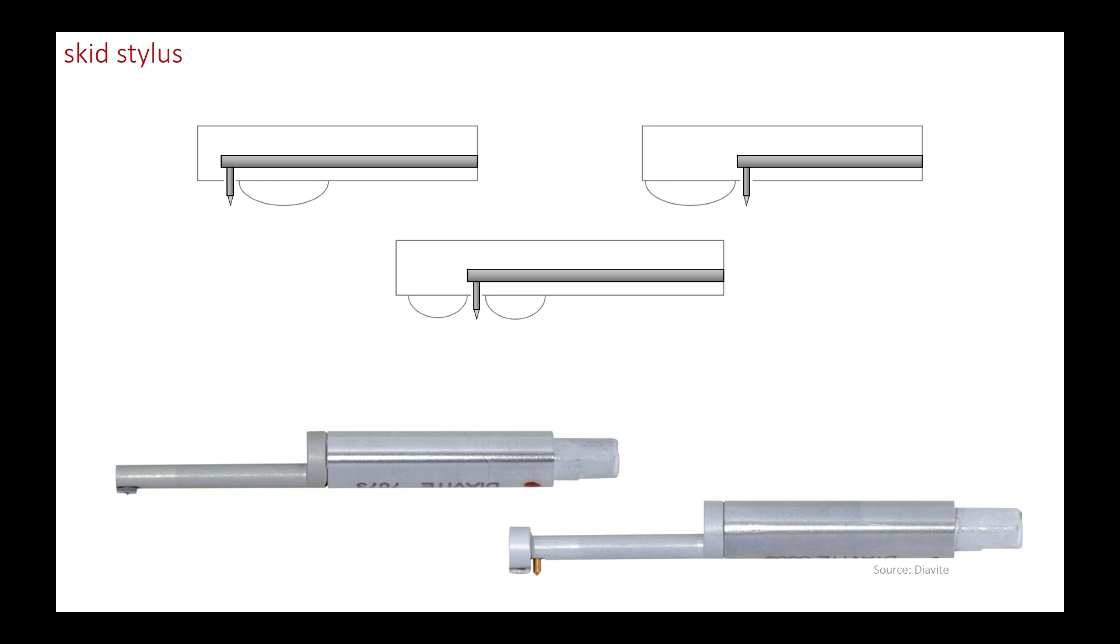As we mentioned above, some profilometers are equipped with a skid. The principle is to have a wide pad in contact with the surface to serve as a reference. This pad smooths the local roughness, allowing the tip to register the differences between this smooth form and the actual relief, thus approximating the roughness.